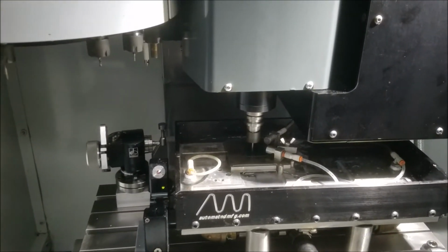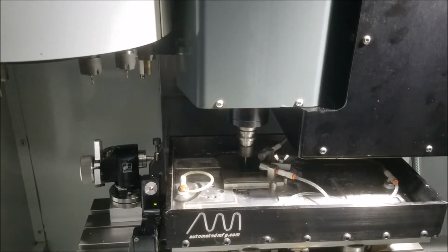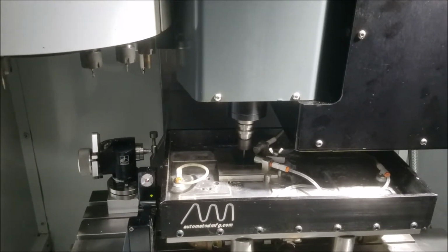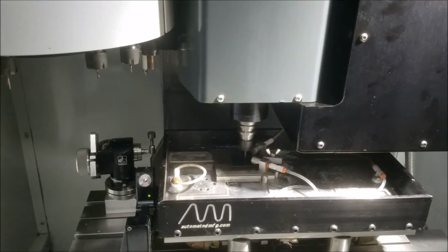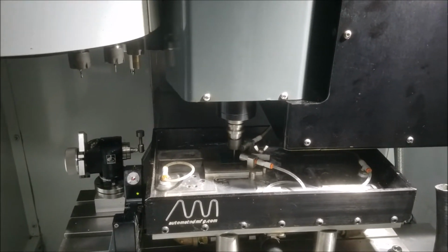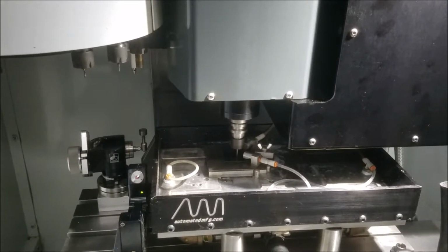There are different cutting operation types. This allows for a fast and accurate sample cut. The cutting path is created by following the profile that either the touch probe or our spectrometer created.